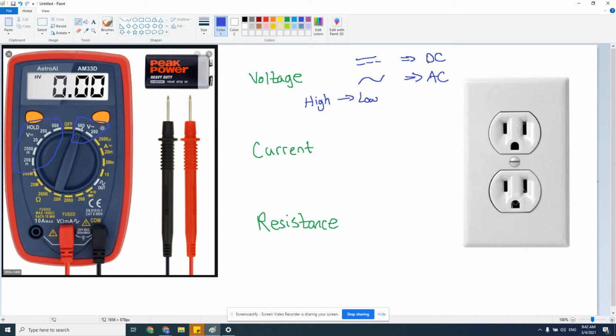So what you would do is dial into 500 first and check the reading. If the reading comes out and says 120, okay good — now you can dial down to 200. Now the meter might say 121.2. So what the meter did is give you a more accurate reading on the lower number, but we start with a higher number to ensure we don't damage the meter.